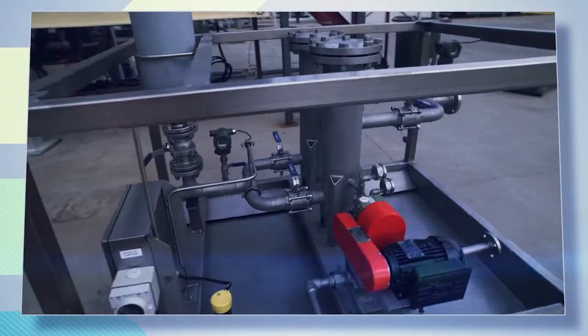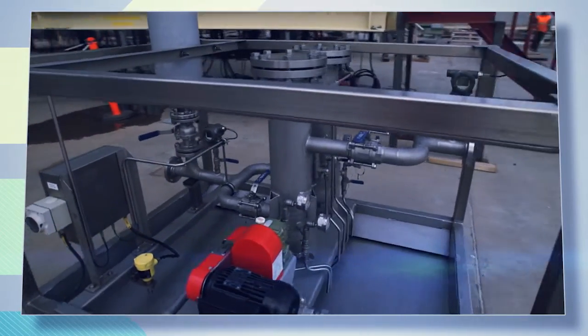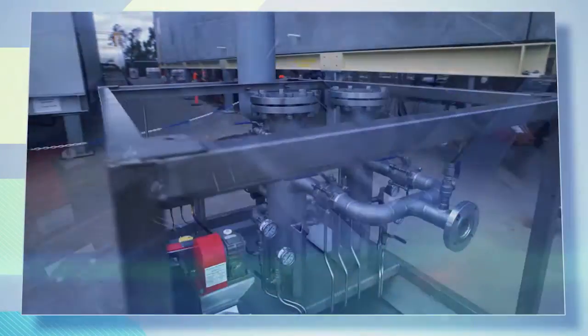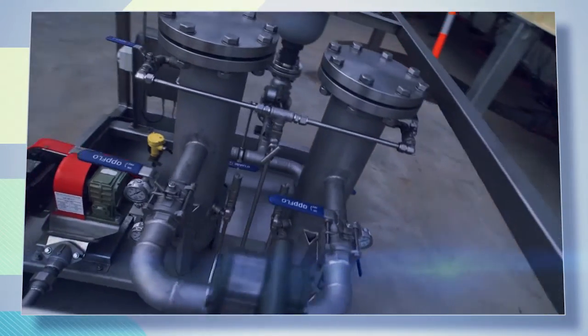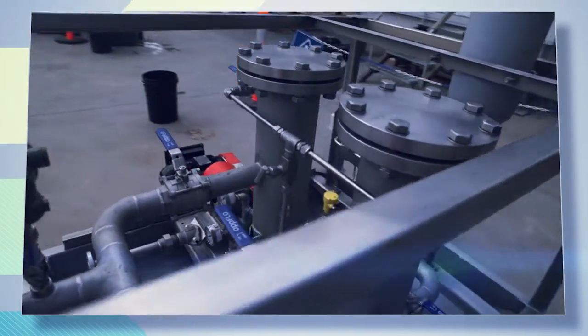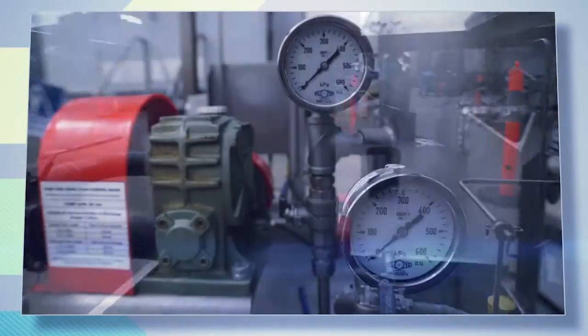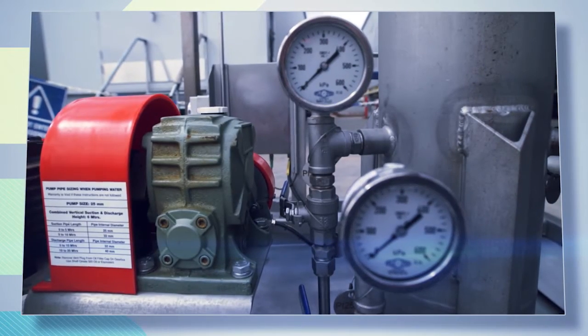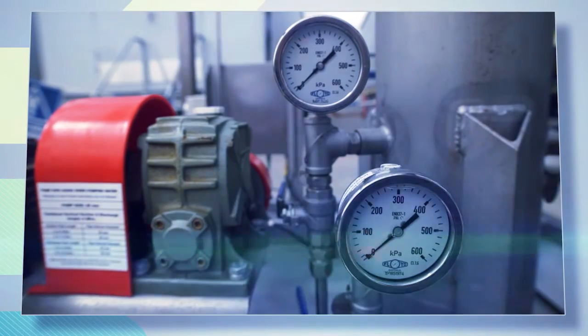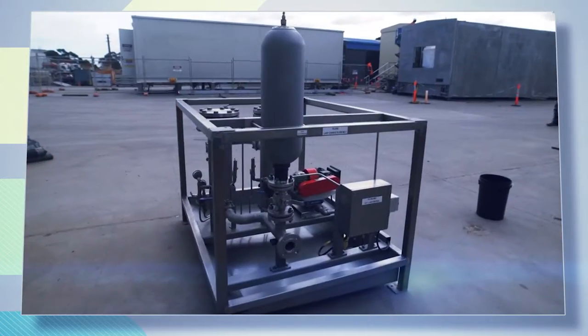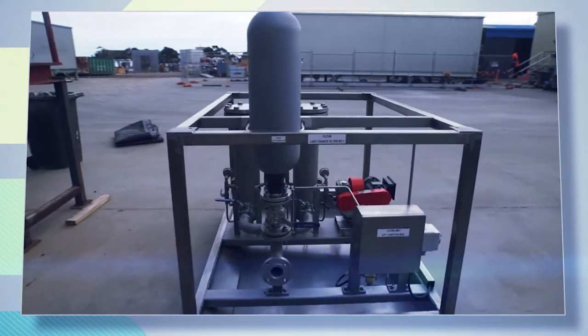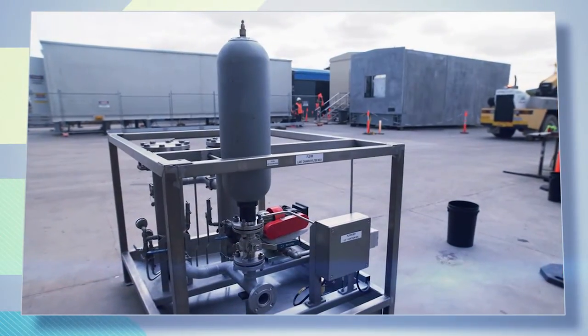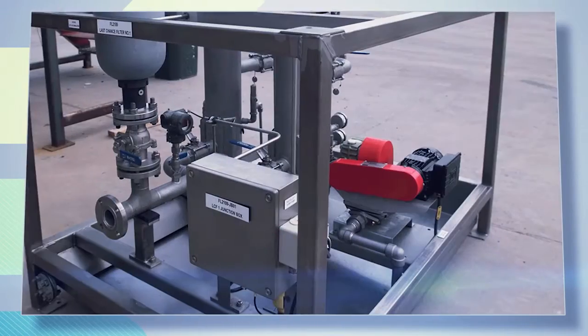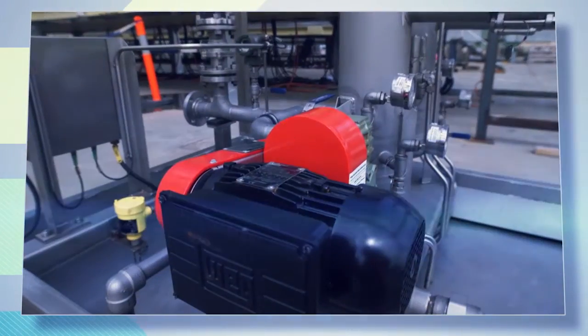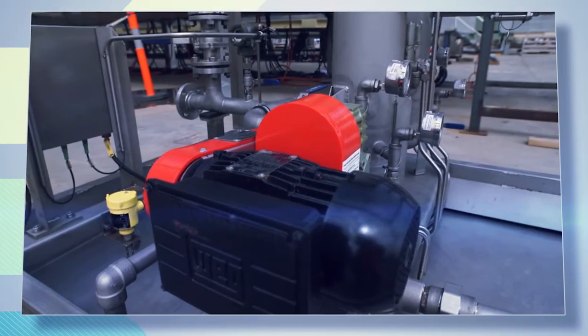The last chance filters are located at the turbines to provide final filtration of clean fuel. The filters are a duplex configuration with individual manual isolation valves. Upstream and downstream pressure instrumentation alerts the operators when a filter is blocked. An accumulator is fitted at the discharge to provide stored fuel for emergency disruption events. A diaphragm-type pump transfers any fuel captured back to the FuelBLOCK sump.